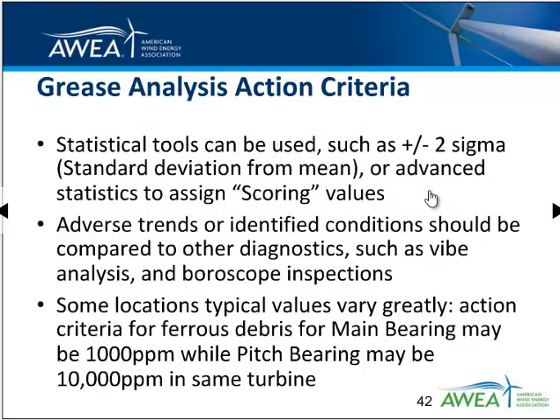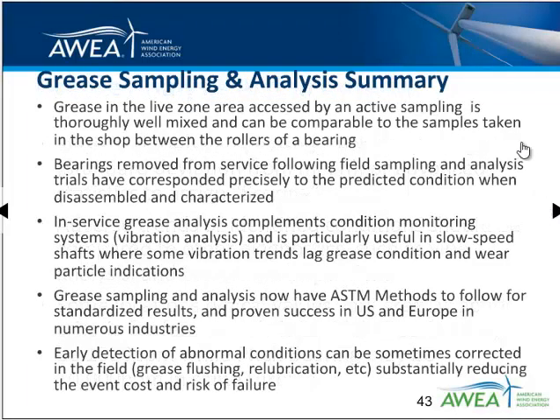Statistical tools such as plus or minus two sigma or advanced statistics can be used to assign scoring values to know which components warrant advanced grease analysis or maintenance targeting. It's important to know that different locations might vary significantly — a main bearing where the criteria for action is 1,000 PPM, while a pitch bearing may be 10,000 in the same turbine. This has to do with the rate of replenishment of grease and the typical levels of wear generated for these locations.